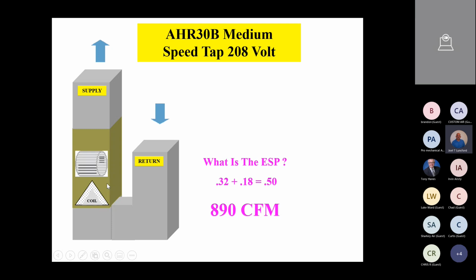Because if you come up here and poke a hole in the cabinet above the coil and you're reading the suck of the fan above the coil, you're going to have an inaccurate reading on the chart. So in real world situations, there are tons of applications where they're on a free-standing metal stand in the closet, and we're not getting to 3 sides of that to drill a hole and stick a tube in.